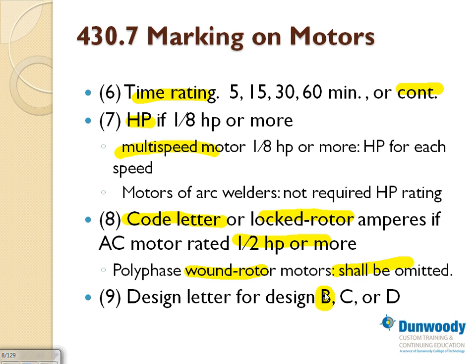Does anybody know the difference between code letter and design letter? Code letter has to do with the inrush. When you have a 100 horsepower motor and push the button to start it across the line, a huge amount of current, for no more than 10 seconds, is going to be sucked out of the system to energize and magnetize the motor so it can start. The question always asks, who cares? Imagine the example we just said, guys. Here's my 100 horsepower motor. When I start this baby across the line, it will be taking almost 6 times more amps than it's running. So to start a 100 horsepower motor, I need 600 amps, only for 10 seconds though.